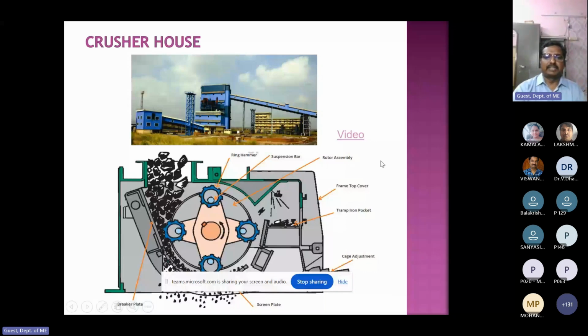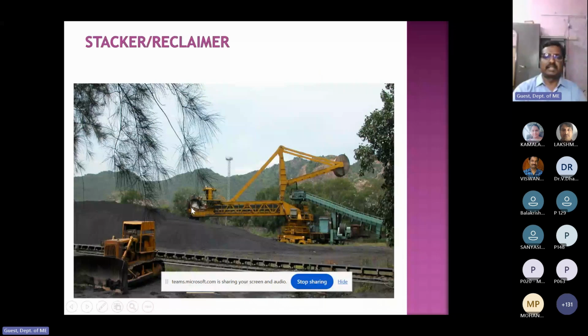These are called heavy equipment in the coal handling plant, called stacker cum reclaimer. That means it will stack the coal when the coal is received, and it can reclaim the coal when coal is deficient. That means it will store. There is a big yard storing the coal. If there is no requirement of the coal, it will be stored with the help of this equipment. In case of more requirement, the same equipment reclaims the coal. This is called a stacker and reclaimer.